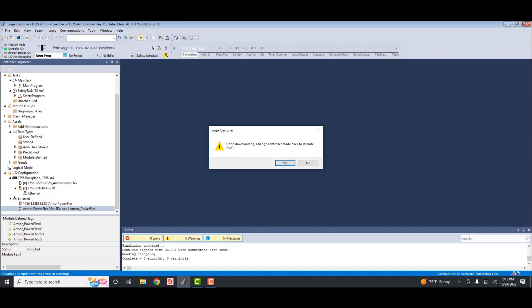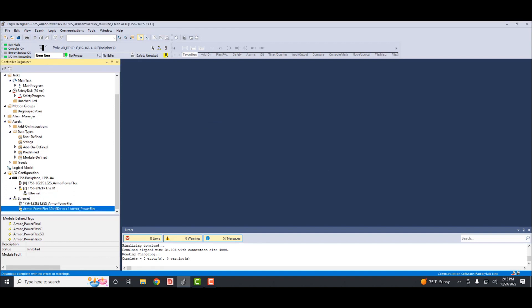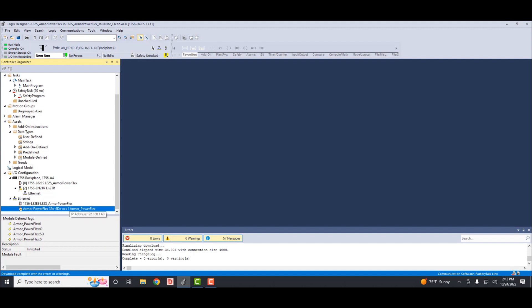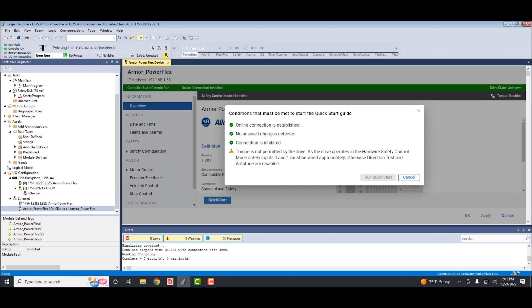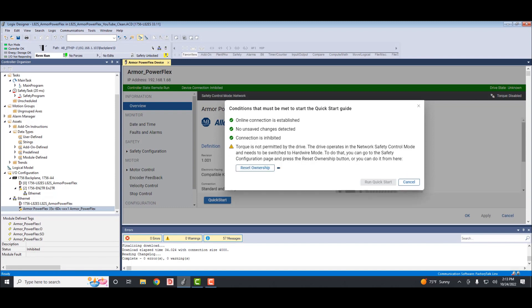Now while online with the project, you can open up the drive properties and do a quick start. Now we can hit the quick start button. Once the wizard opens, it'll want you to confirm the drive needs to put itself into hardwire safe control. All Armor PowerFlex drives come with a red safety jumper and it must be plugged into one of the safety inputs on the drive. I'll plug it into the top, which is the safety input 0 and 1. Now that the drive recognizes it, you'll be able to reset ownership and/or run the quick start.